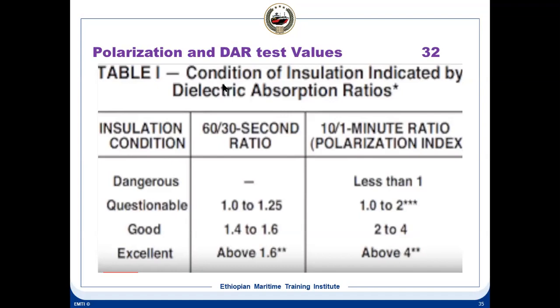Because with high voltage, we have very high insulation compared with low voltage. Whether it is a cable or a winding, whatever it is, the insulation thickness is very high. That is why we go for this PI test. Otherwise, for things with low insulation, the normal insulation test is good enough to measure it. You understood?